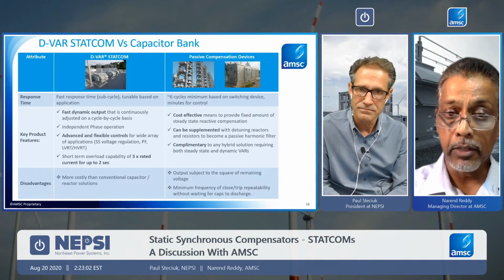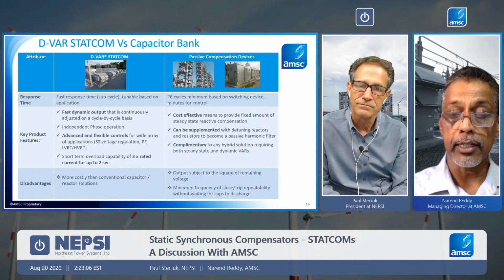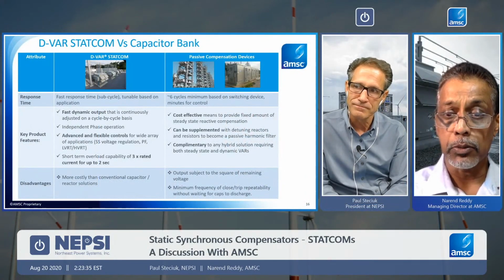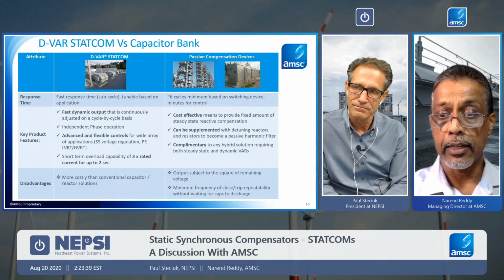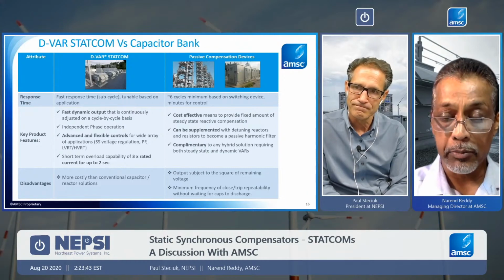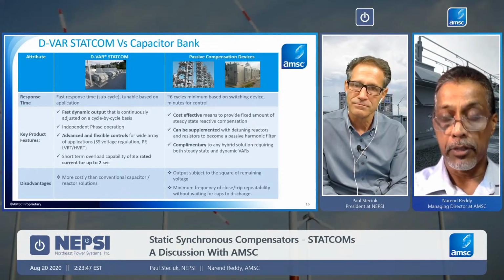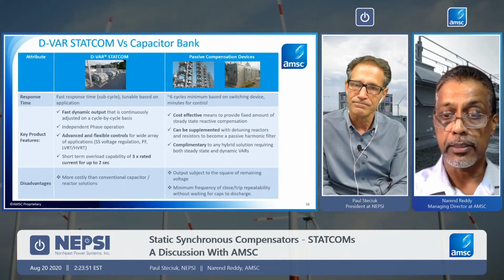But the neat thing is also that more and more what we're seeing is that we are selling STATCOM systems that are hybrid. Hybrid means that you have a certain portion of the system as STATCOM, and a certain portion with cap banks or reactor banks. I'll talk a little bit later in the presentation on that one. Some of the disadvantages, obviously, STATCOM is a little costlier and more expensive. For the cap banks, the output is subject to the square of the remaining voltage. There are limitations in terms of how many times you can switch it in and out, but there are ways that we can improve on that using discharge capacitors, discharge reactors and things like that. I think we'll cover some of this later on. But hopefully, I've covered some of the things that you're looking for, Paul.